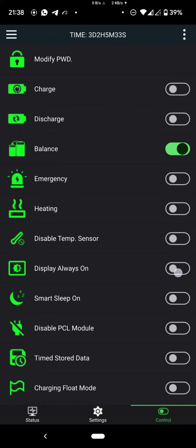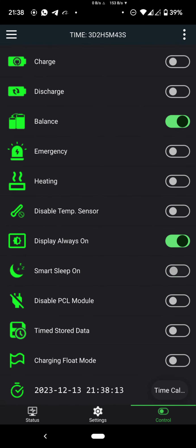Display always on. This will keep the display always on. I have a 7-inch display and I keep it on all the time. Smart sleep. There's a parameter where you can set some time, for example, 24 hours. If the BMS is idle for 24 hours, it will turn off, I guess. Time stored data. I think this is used to include data and time with the warnings and errors. And this is where to calibrate the date and time. It is fetched from the phone's date. Also, we have the floating mode enable and disable. This is the switch for floating mode.